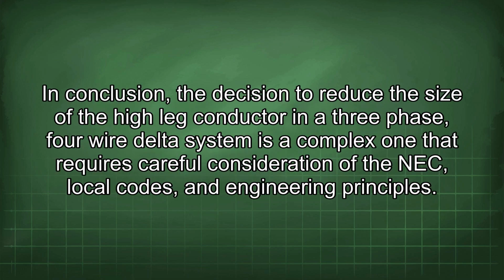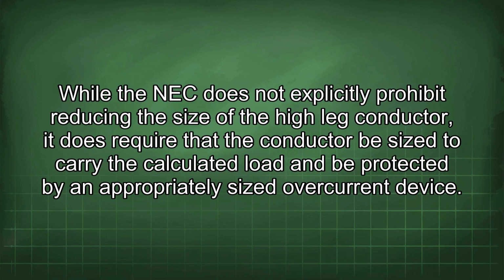In conclusion, the decision to reduce the size of the high-leg conductor in a three-phase, four-wire delta system is a complex one that requires careful consideration of the NEC, local codes, and engineering principles. While the NEC does not explicitly prohibit reducing the size of the high-leg conductor, it does require that the conductor be sized to carry the calculated load and be protected by an appropriately sized overcurrent device.